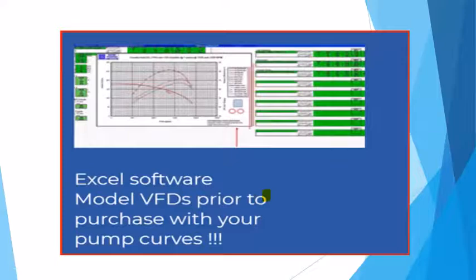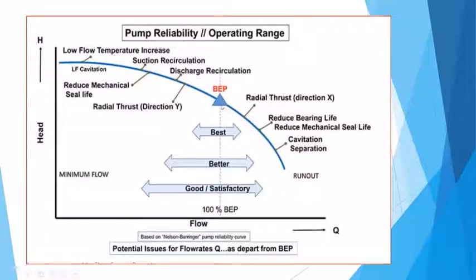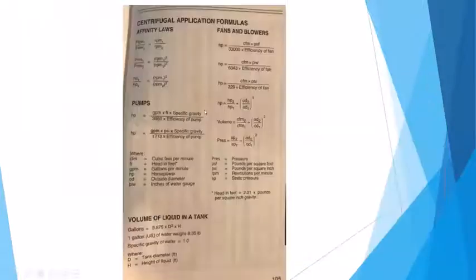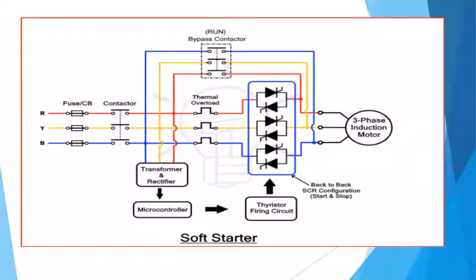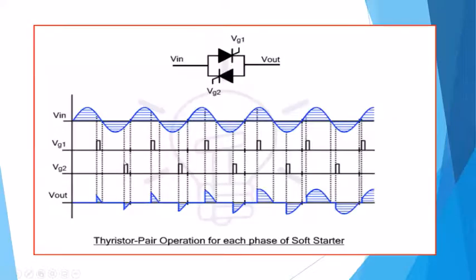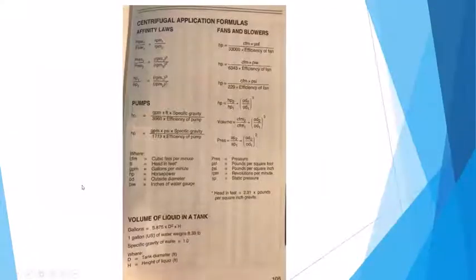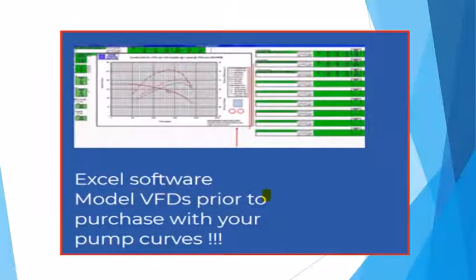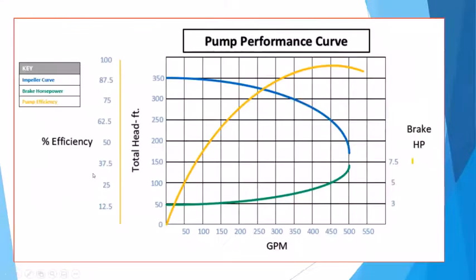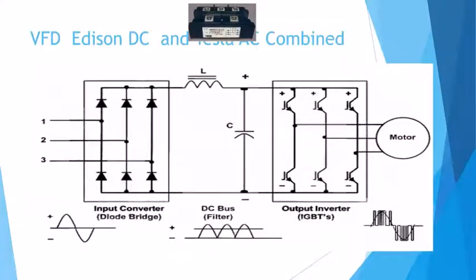So if you design your pump to operate at your best efficiency point, and you go back to what I was showing you originally on the soft starter, the only losses in there are the thyristors. And then once they're up and running, this contactor bypasses. So you literally eliminated that 5 or 6% loss that happens with a VFD. But it does require more calculations and design to get to the optimal efficiency point. So you maybe do not need a variable speed drive, and just use a soft starter to soft start the water hammer, both up and down in speed. You can do that with a soft starter.